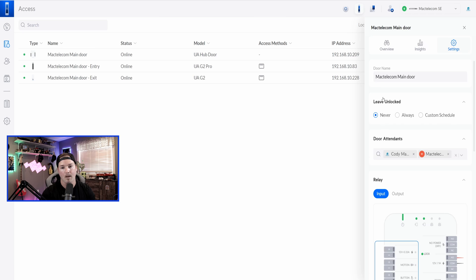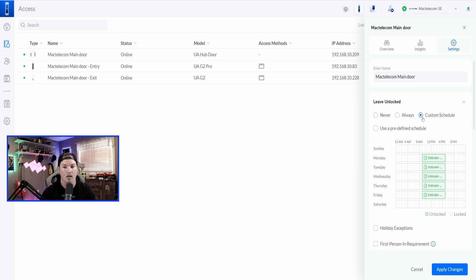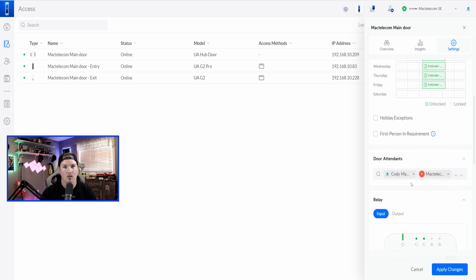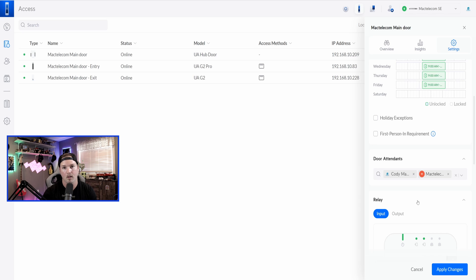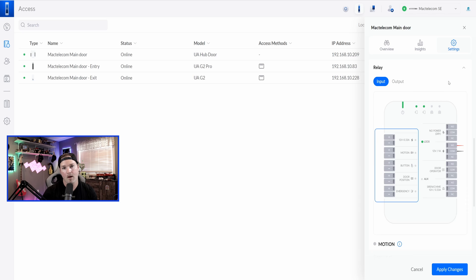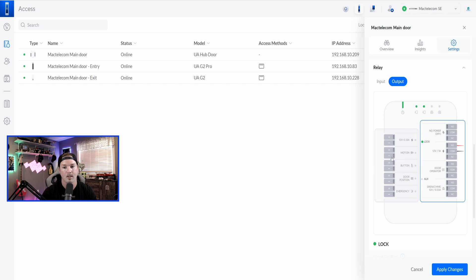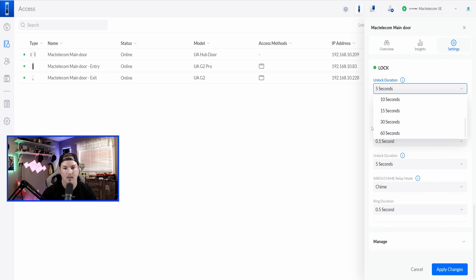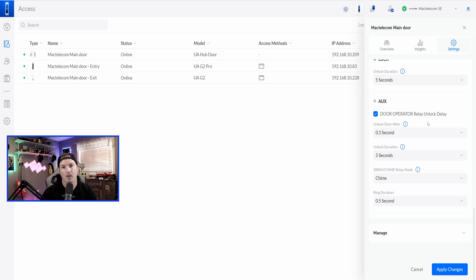Under the settings, we have our door name, and then we have leave unlocked. So we could have this never unlocked, we could have it always unlocked, or we could do a custom schedule. So say from nine to five during working hours. Now, say we had our custom schedule, but we didn't want it to unlock until the first person swiped in, and that's what this is right here, first person in requirements. We have a couple different door attendants, so that's just some users. If somebody calls into the door, they could swipe to call, the door attendants will get that call. We have our different relays. So we have our input relays, and then we have our output relays, and they have redesigned how this graphic looks, and it's really nice. We have our lock duration, which is 0.1 second all the way up to 60 seconds, as well as our aux and our door operator relay unlock. If we end up putting a siren or a chime, we could change that down below as well.